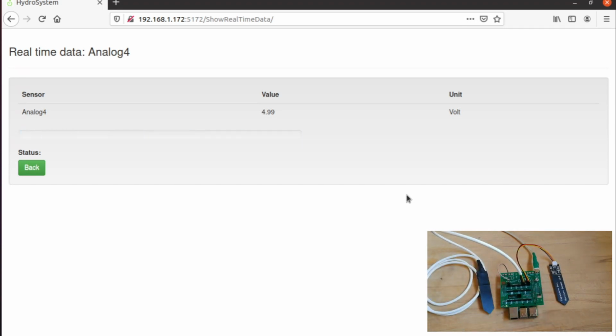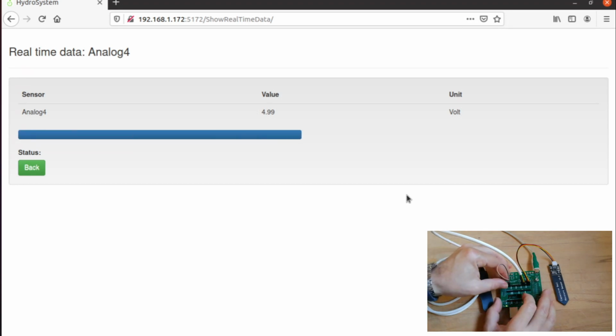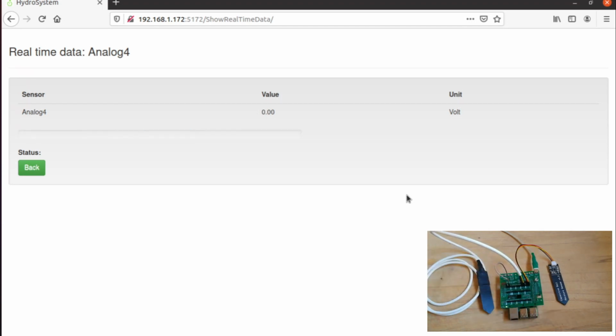You see, the reading is now 4.99. That is not exactly 5 volts, but it's very close. And then I can check again, putting the jumper in short circuit with the ground, and we have the 0 reading. So with one jumper you can do a very simple test and check if the input is working. If the input is working, as this is just an analog input, and you don't see a good reading, it means that the sensor has some issues.